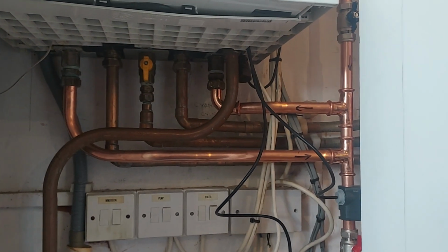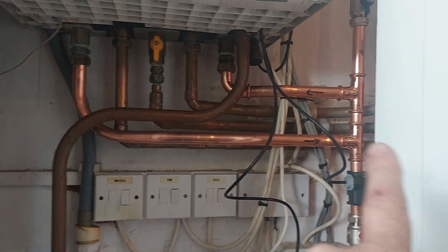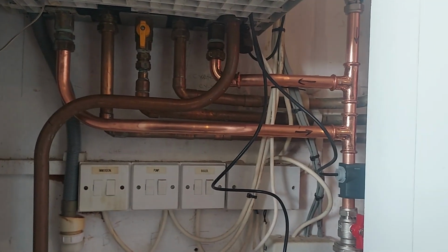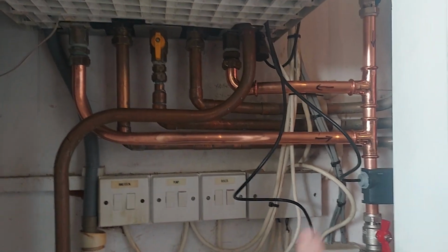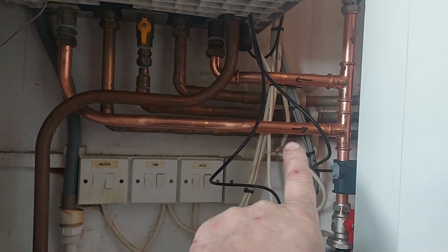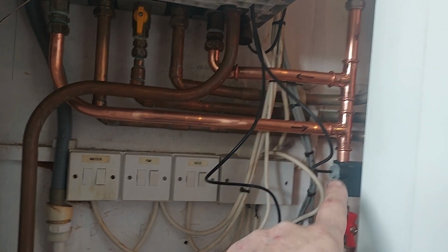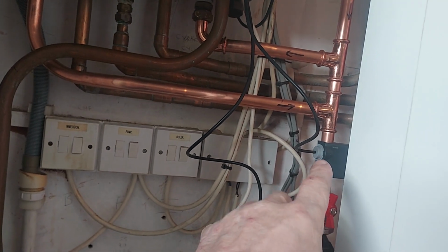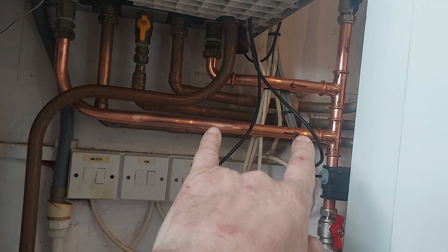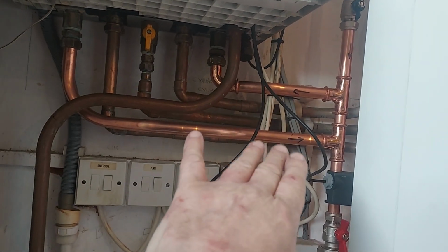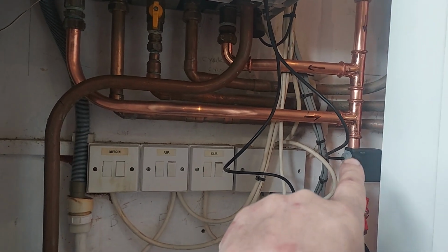The amount of energy required by the system is dependent on, obviously, the load outside, but also the temperature required to go into the system to satisfy the load. So if I'm hitting target temperature, let's say my target temperature for this underfloor is 30 degrees, and I'm hitting 30 degrees on my mixed point, actually this point here, then the boiler will see that it doesn't require any more energy. It's going to back off and back off to a point where it's only putting the energy in required to maintain the 30 degree flow.